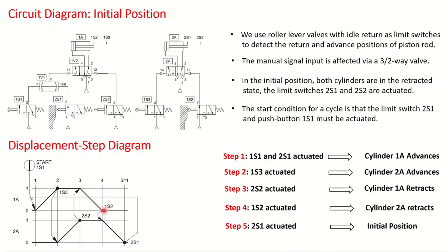From 1S2 we have an arrow indicating the retraction of the second double-acting cylinder begins. It reaches back to 2S1, shown as step 5 equals step 1, meaning we are at the beginning of a new cycle and the pneumatic circuit is ready to start again. That is how we read a displacement step diagram. Sometimes we have a drawing and must write the displacement diagram; other times we have a problem statement and must provide both the displacement step diagram and the pneumatic circuit.